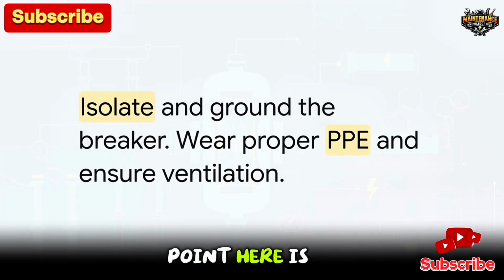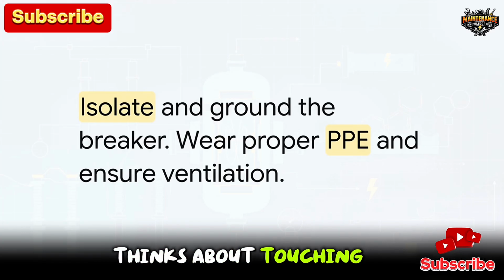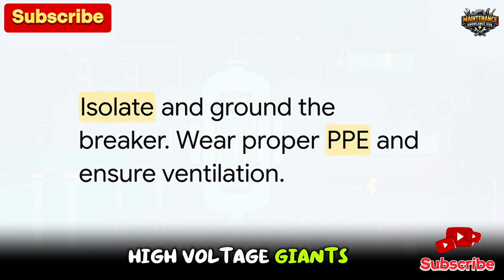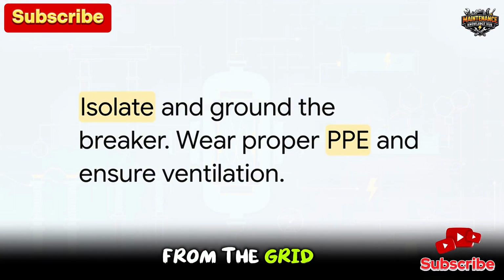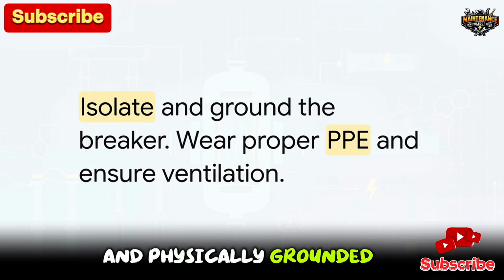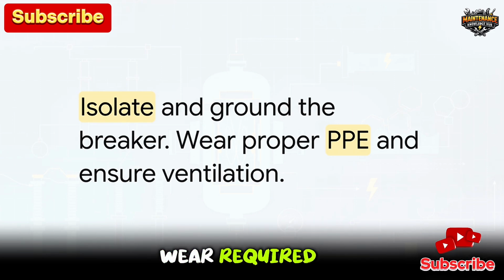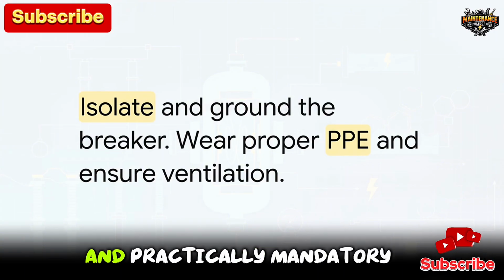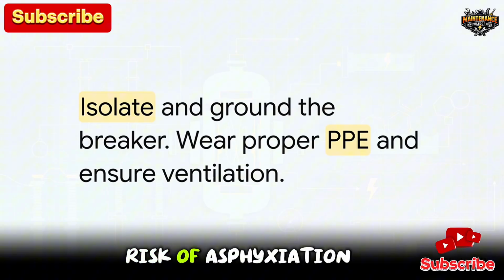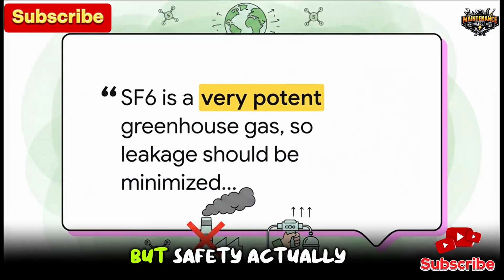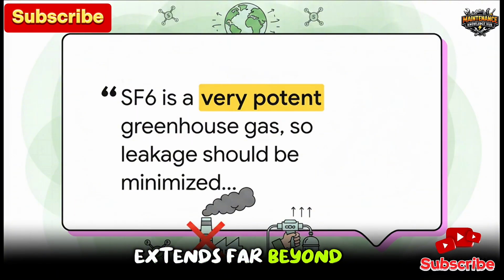All right, let's wrap things up with Section 6, Safety and Environmental Impact. So the crucial point here is, human safety always comes first. Before anyone even thinks about touching these compact, high-voltage giants, the breaker must be entirely isolated from the grid, strictly locked out, and physically grounded. Technicians have to wear required personal protective equipment, which includes arc-rated clothing and thick insulating gloves. Furthermore, because they're dealing with heavy gas compartments, adequate ventilation is legally and practically mandatory to prevent any risk of asphyxiation in confined spaces.